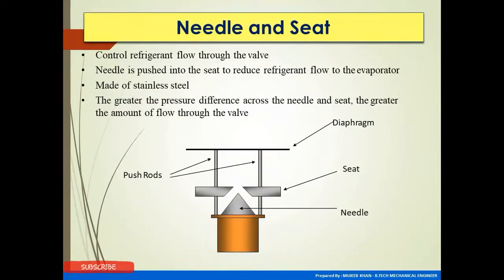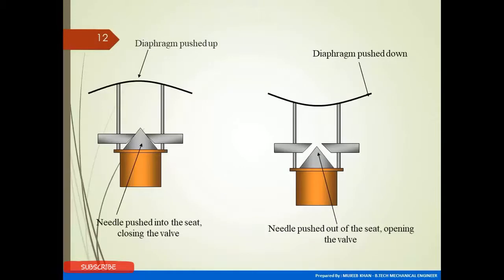Needle and seat control refrigerant flow through the valve. The needle is pushed into the seat to reduce refrigerant flow to the evaporator; it is made of stainless steel. The greatest pressure difference across the needle and seat produces the greatest amount of flow through the valve. When the diaphragm pushes up, the needle pushes into the seat, closing the valve. When the diaphragm pushes down, the needle pushes out of the seat, opening the valve to allow refrigerant to flow.